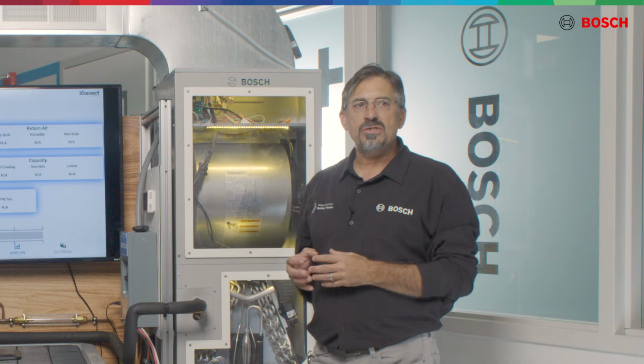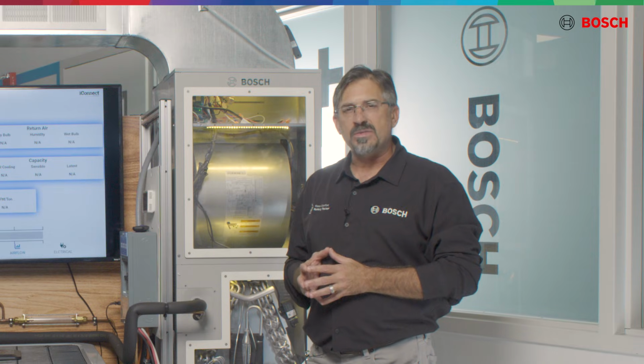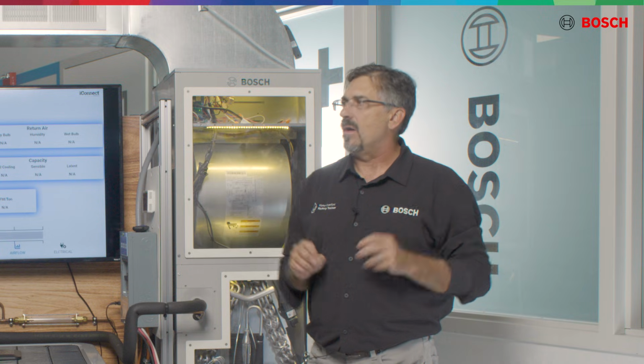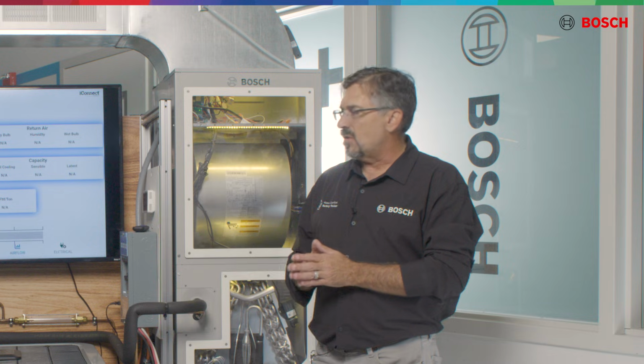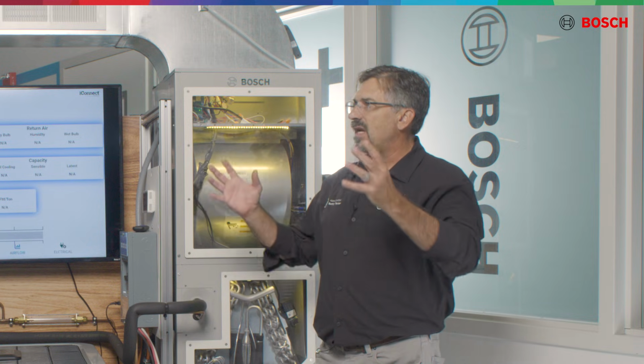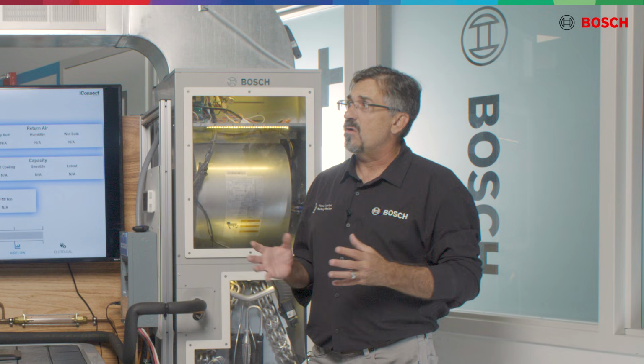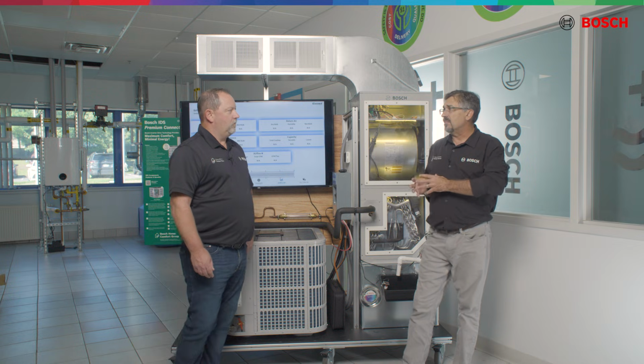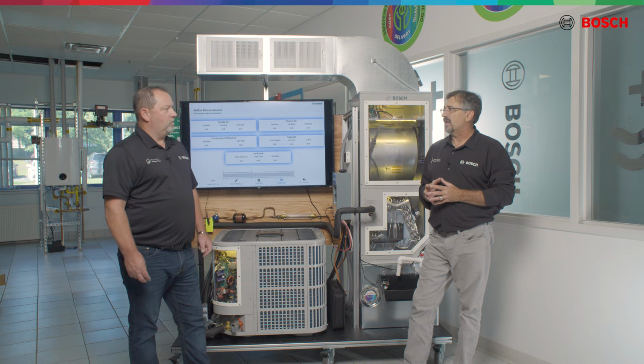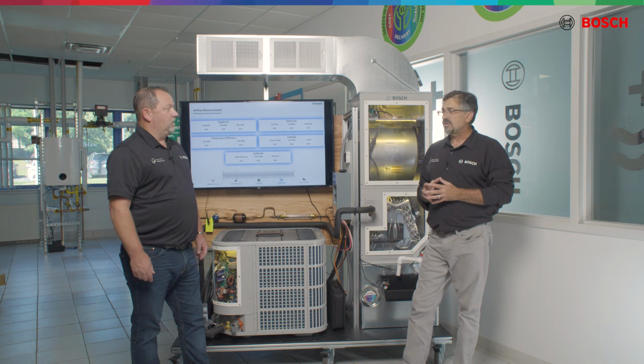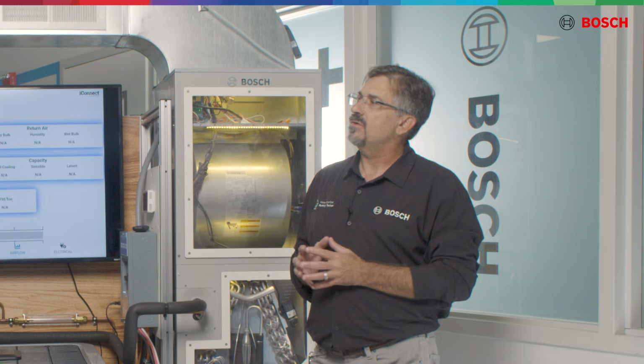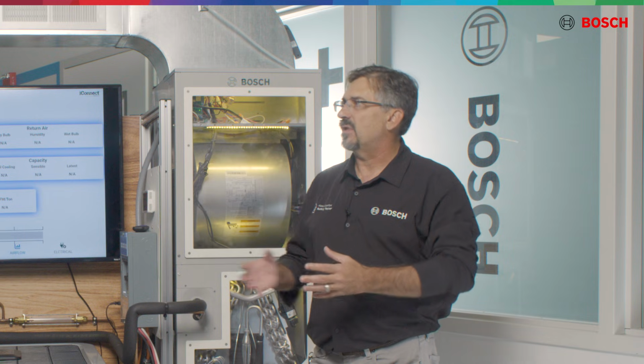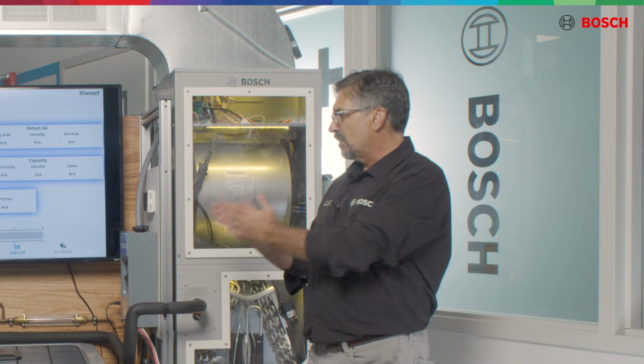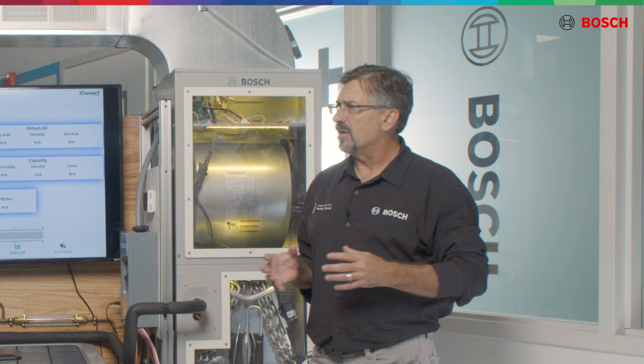Okay. One of our number one issues with our tech support team is the call comes in, our system doesn't keep up. Not like our old system did. Yeah. So the end user, the homeowner, wants to know, why does this new system not operate like my old system? And that is re-educating our contractors as well as our homeowners. Okay. Filters are one of the biggest things in our industry that are overlooked of being a problem. So I just can't use any filter I want? No, you certainly can't. The only time you can use any filter you want is when you prove your static pressure is within our Bosch blower performance data, proving this system can perform in the environment you installed it in.